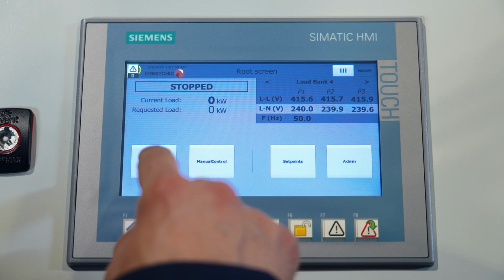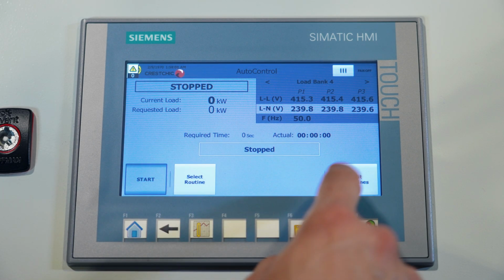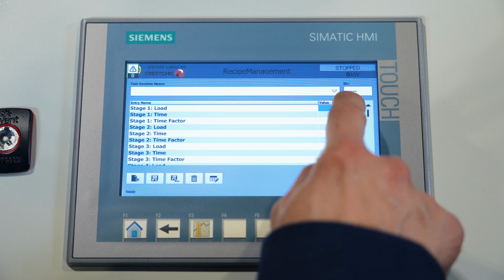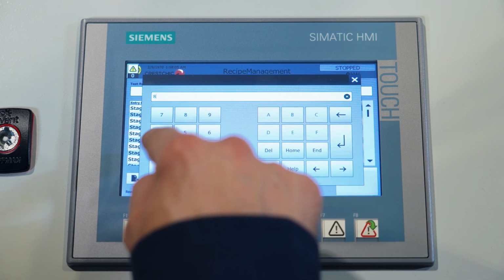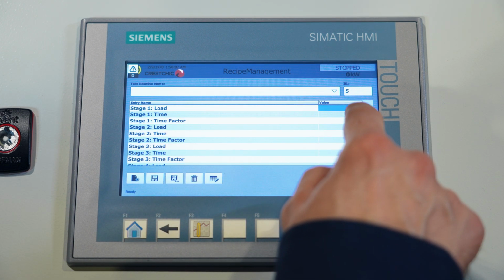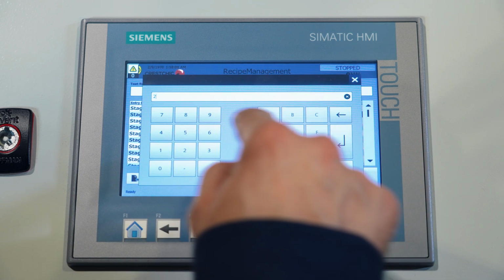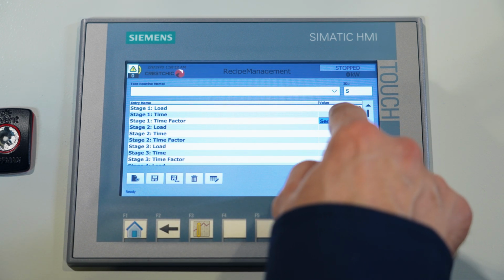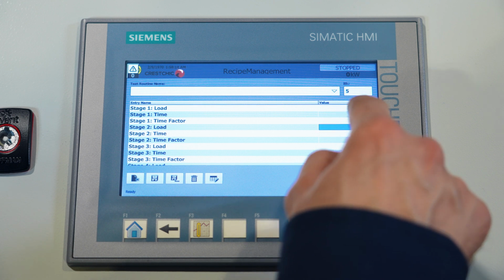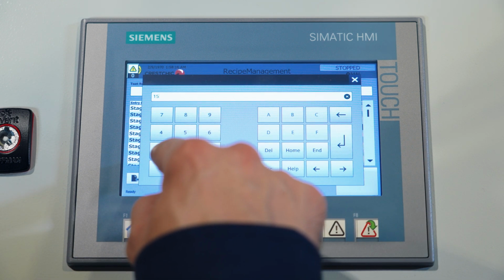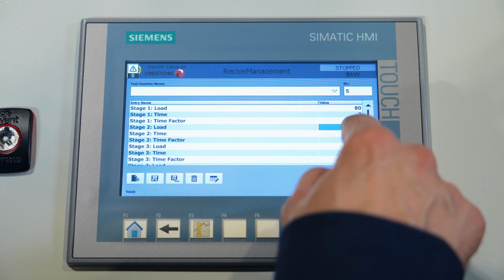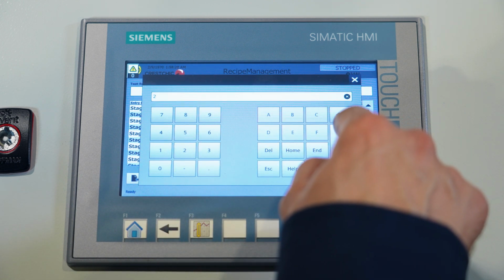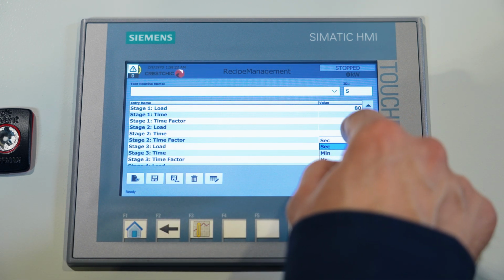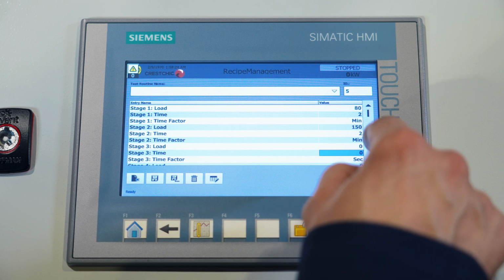The second method of applying loads is an automatic test, where different size loads can be programmed for a set amount of time, and the digital controller will automatically change the loads according to this program. This therefore means that from pressing start on the controller until the test has been completed, the operator does not need to control the load banks, but simply monitor the test. The program can be programmed on the digital controller or can be uploaded to the controller via a USB stick.